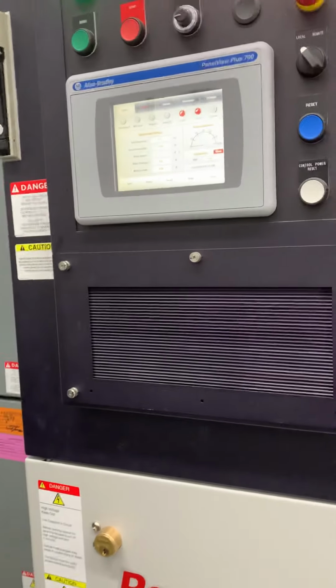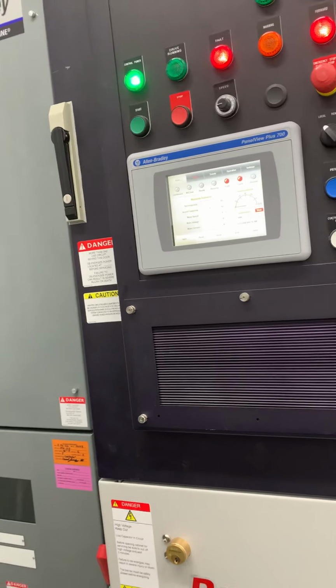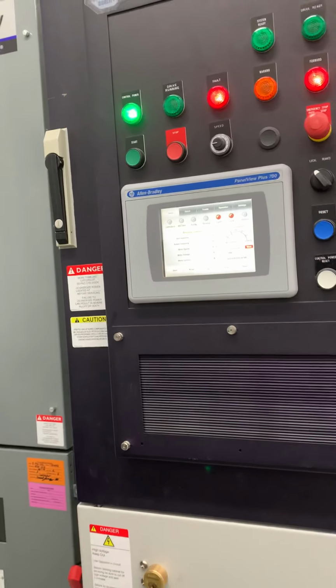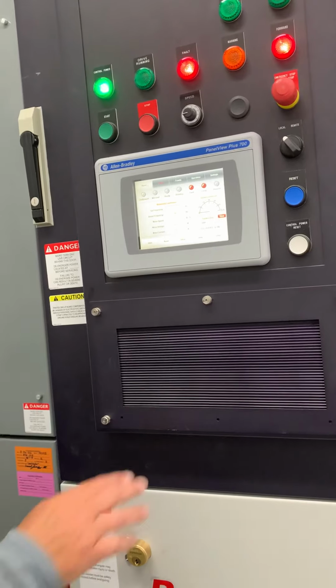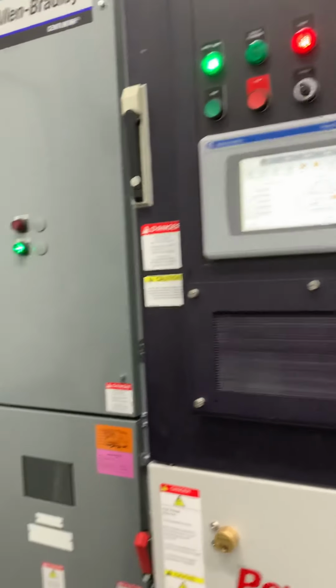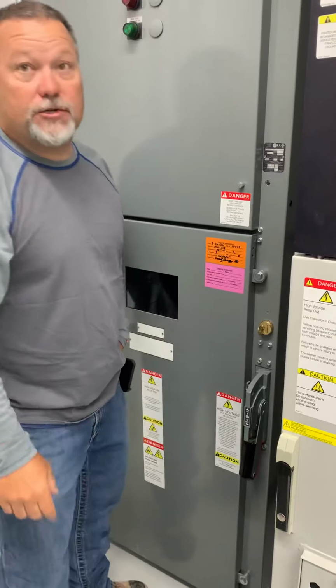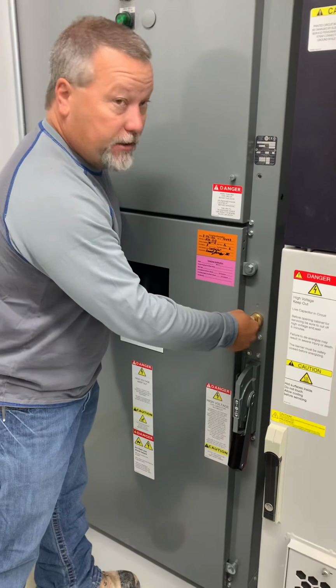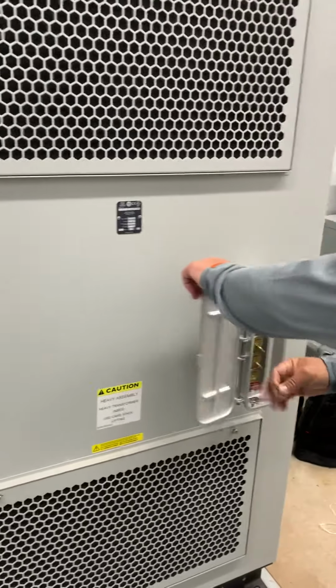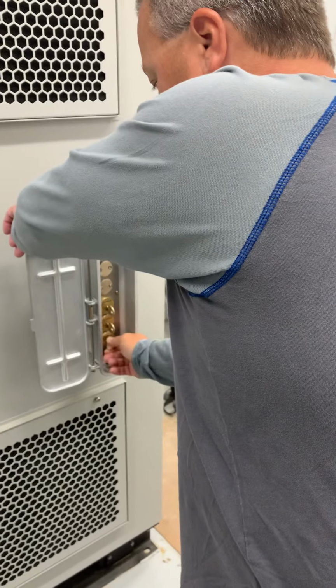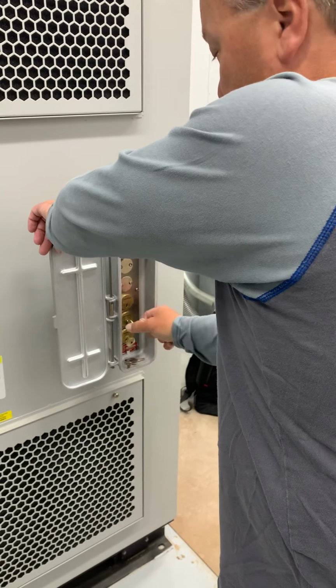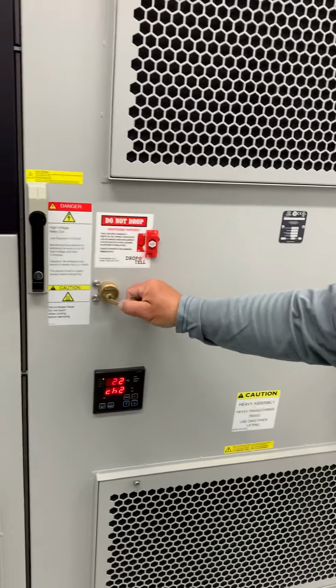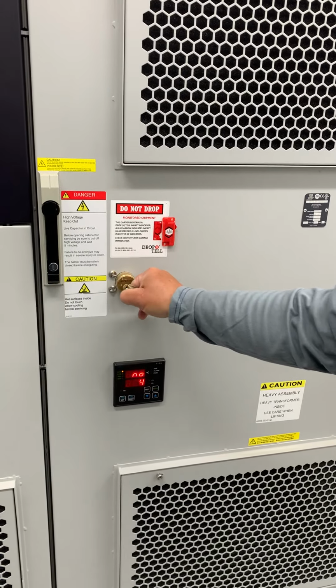Now the other thing you got to remember about these: if you want to get into the panel and look inside the panels, or if you call tech support and they say, "Hey, you need to look at this," in order to get inside these panels, you have to have this e-stop pressed, of course. You have to open up the switch, lock it out. Kirk key. In order to open those panels, turn your Kirk key, and that allows you to pull these two keys out. That'll allow you to open up these locks, to open up these panels, and it keeps you from getting anywhere that has 4160 on it.